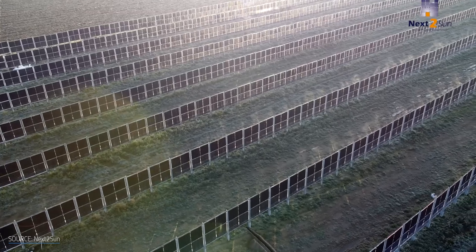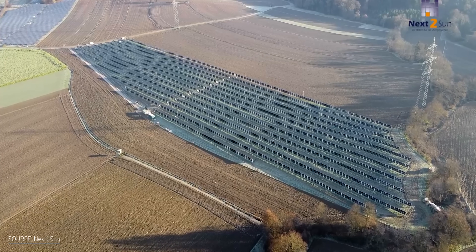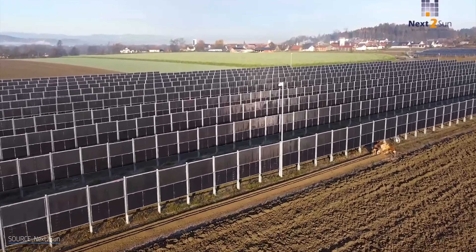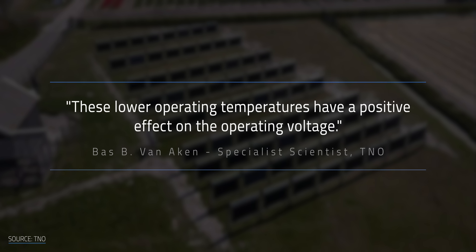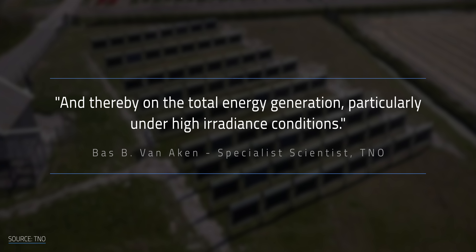Why? Their heat transfer coefficients — a figure that defines how heat energy passes from one material to another — are much lower than expected. This means they remain much closer to the ambient temperature, only about half as hot as their horizontal counterparts, likely because their orientation means they can dodge some of the worst of the heat. These lower temperatures mean less voltage is lost to overheating, which allows the vertical bifacial solar panels to generate more energy overall. As paper author Bas B. Van Aken put it: these lower operating temperatures have a positive effect on the operating voltage and thereby on the total energy generation, particularly under high irradiance conditions.